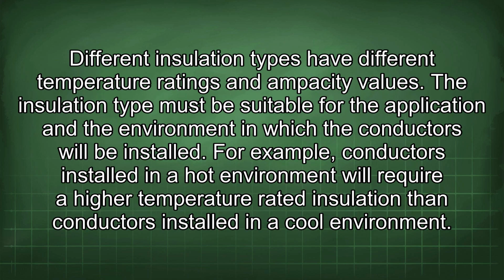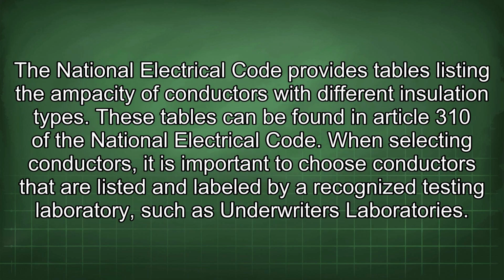Different insulation types have different temperature ratings and ampacity values. The insulation type must be suitable for the application and the environment in which the conductors will be installed. For example, conductors installed in a hot environment will require a higher temperature rated insulation than conductors installed in a cool environment. The National Electrical Code provides tables listing the ampacity of conductors with different insulation types. These tables can be found in Article 310 of the National Electrical Code.